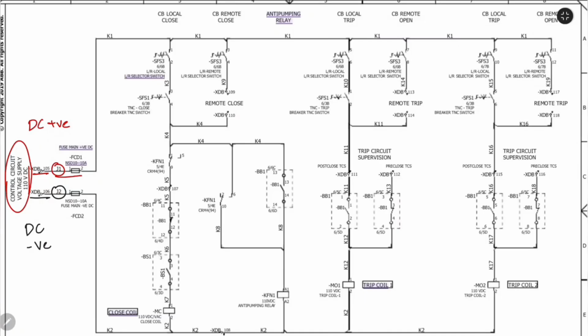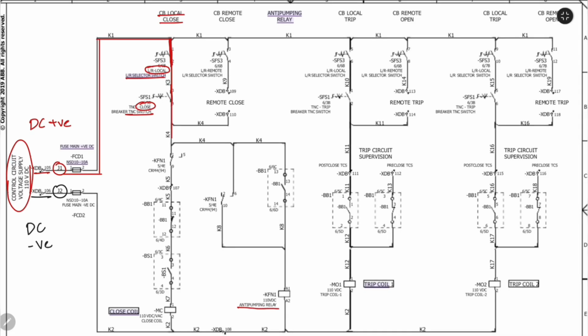Let's now understand how the breaker closes in local mode. Turn the local remote switch to the local position. This closes the local contact and routes the DC positive from terminal J1 to point K3 on the TNC switch. When the TNC switch is turned to close, the positive supply moves from K3 to K4. The current now passes through the anti-pumping relay KFN1. Since the relay is de-energized, its normally closed contact allows the positive supply to continue toward K5.